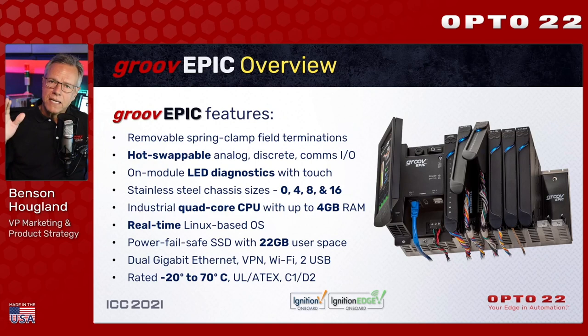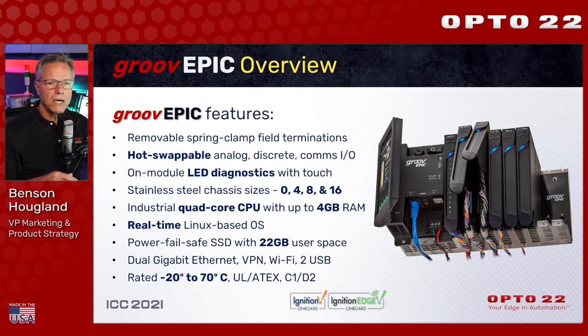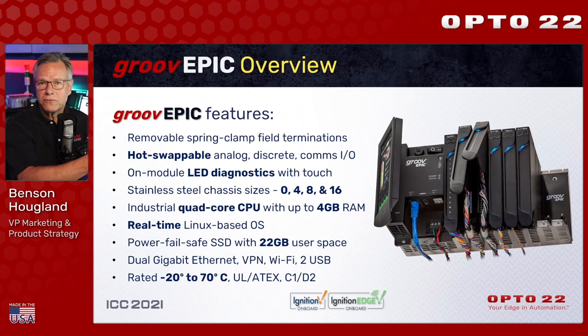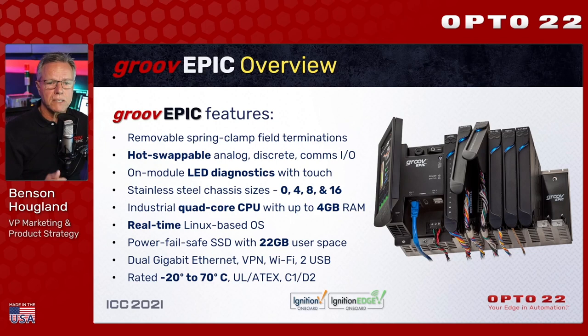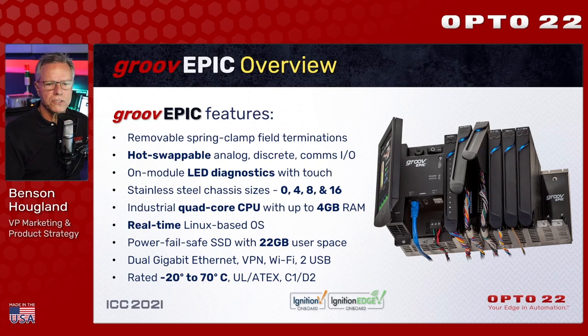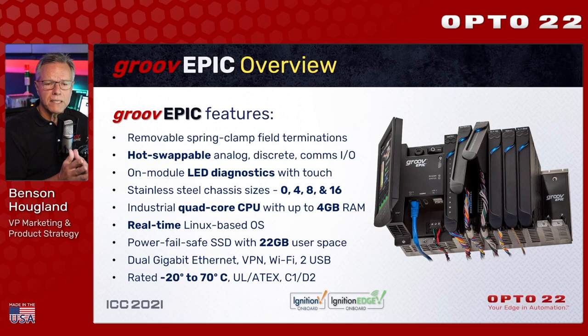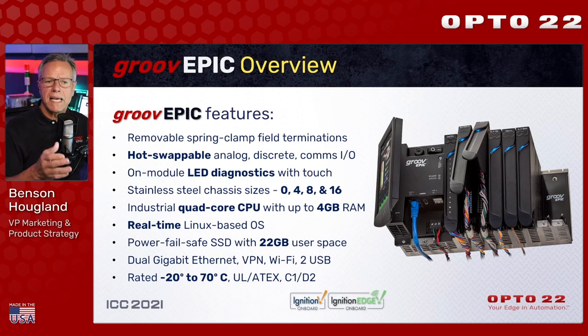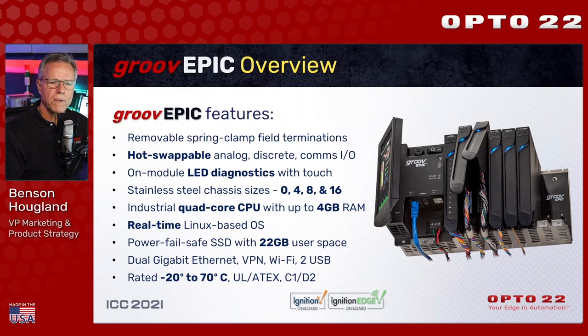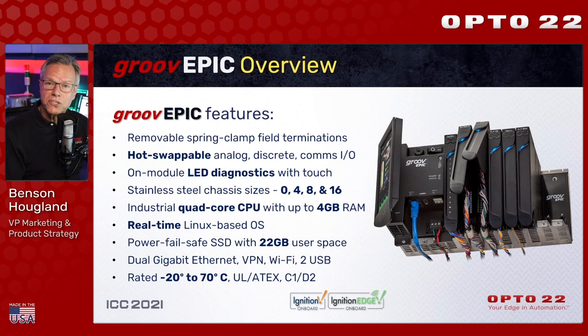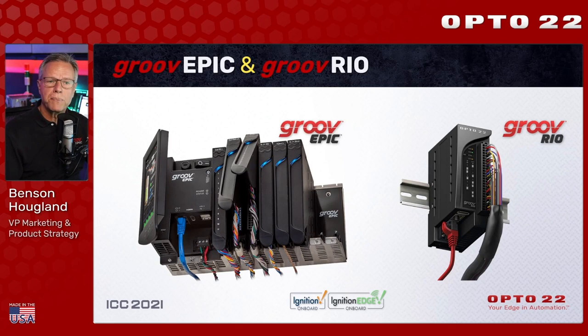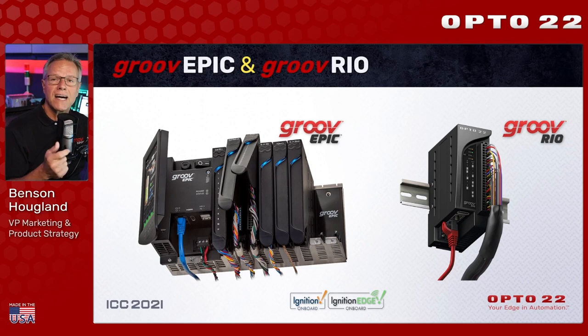From a hardware perspective, we're packing quite a punch here from hot swappable IO modules and numerous signal types to visual diagnostics and an onboard smartphone size display. The IO is optional - you can get this without any IO modules just to use the gateway features. And that's where the chassis sizes come in, including a zero chassis. It all comes back to a very powerful quad core CPU with a real-time Linux OS, plenty of RAM to run all your software applications, a power fail safe solid state drive with lots of gigabytes of storage available. But most importantly, this comes with multiple network interfaces that will lay the foundation for a secure edge computing platform for your existing unsecured legacy PLCs and devices.